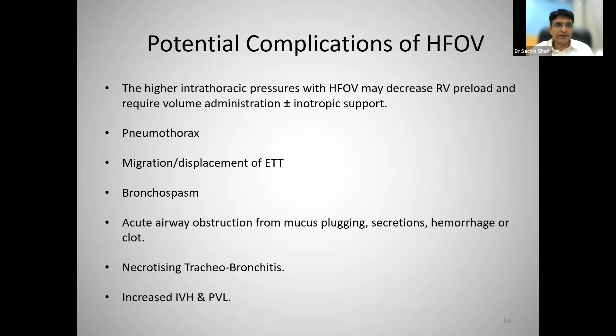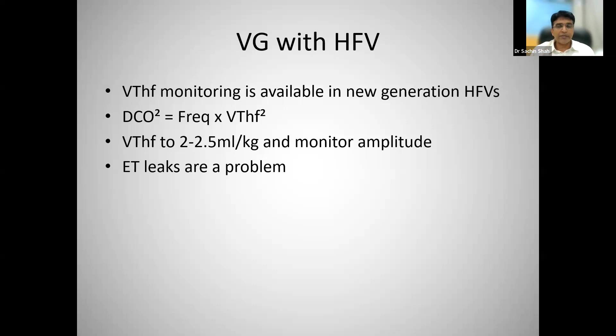Increase in IVH and PVL was there in the older trials, but not seen in the recent machines, and with a good lung recruitment strategy now. Newer machines, as I told you, are monitoring the volumes now, and as Dr. Archana told, volume guarantee along with high frequencies is a newer mode which is available now in some ventilators. So you target your volumes and then you fix your volume guarantee. The amplitude, the machine will decide on its own, like it does in the conventional volume guarantee mode. Leaks can be a problem, so you have to monitor that and you need a good sensor for it.